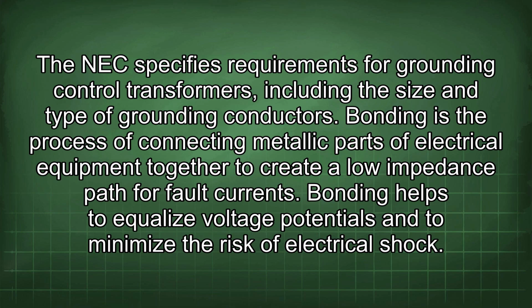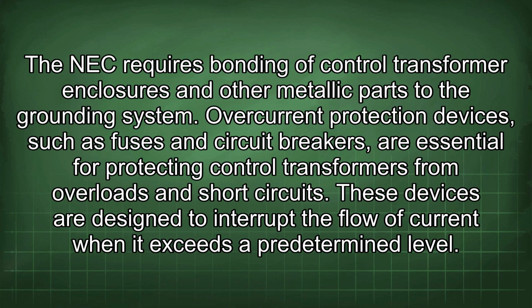Bonding is the process of connecting metallic parts of electrical equipment together to create a low impedance path for fault currents. Bonding helps to equalize voltage potentials and to minimize the risk of electrical shock. The NEC requires bonding of control transformer enclosures and other metallic parts to the grounding system.